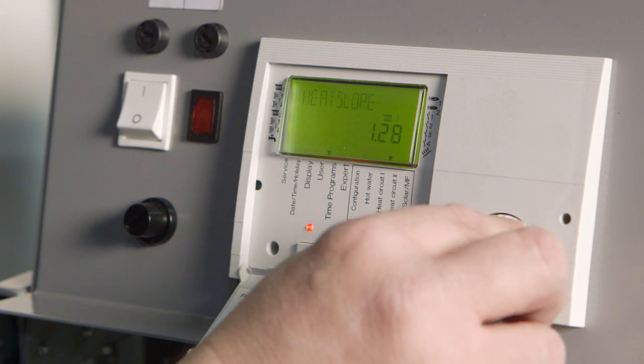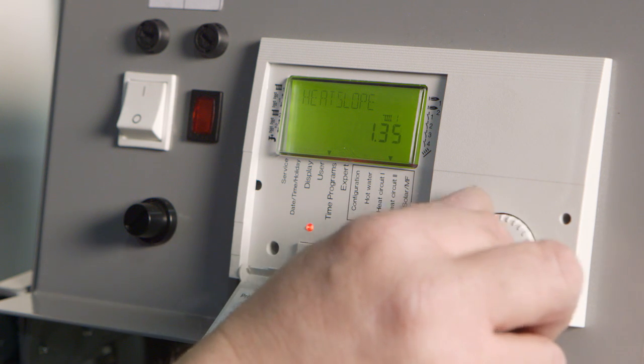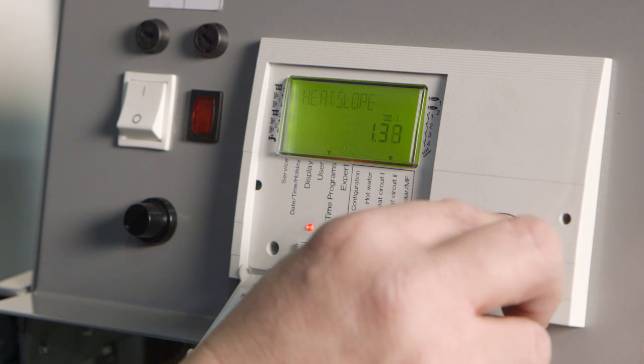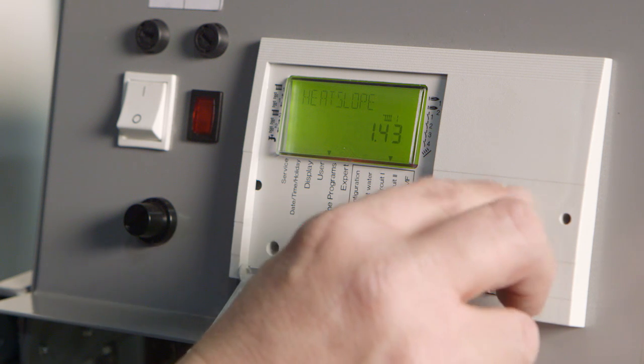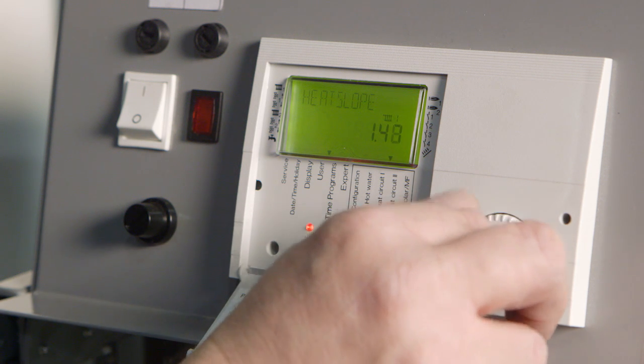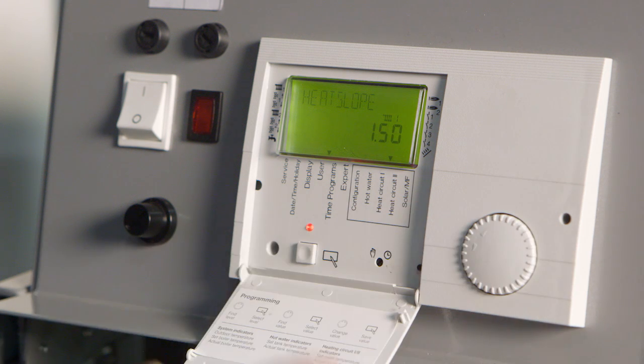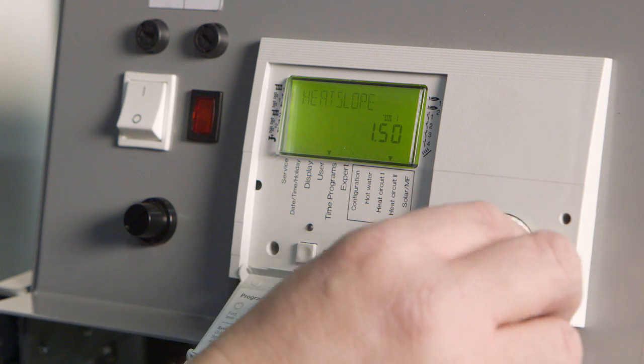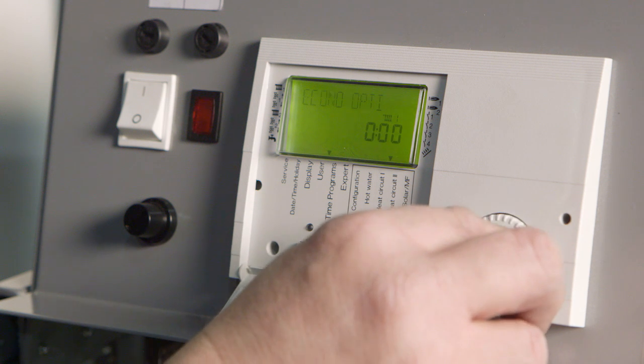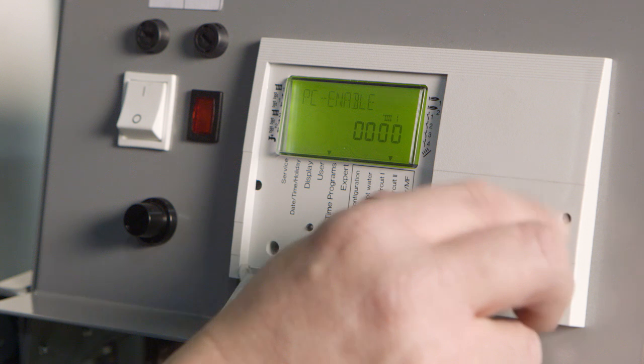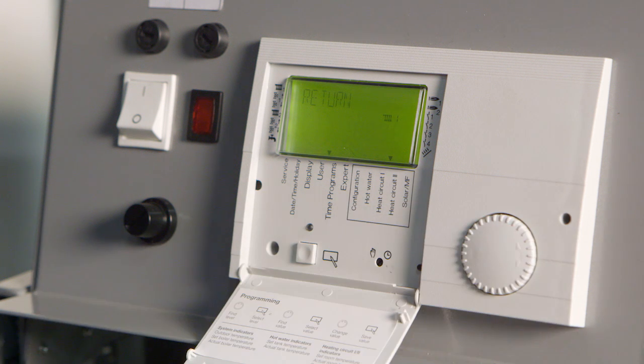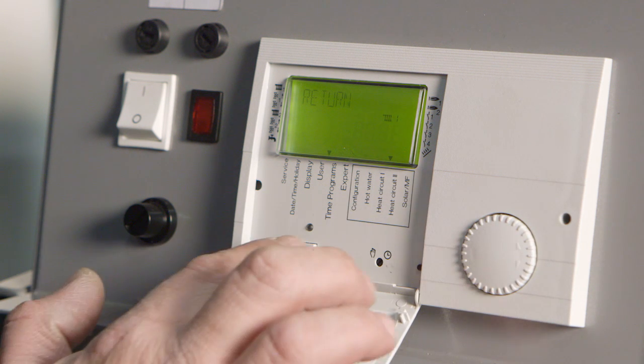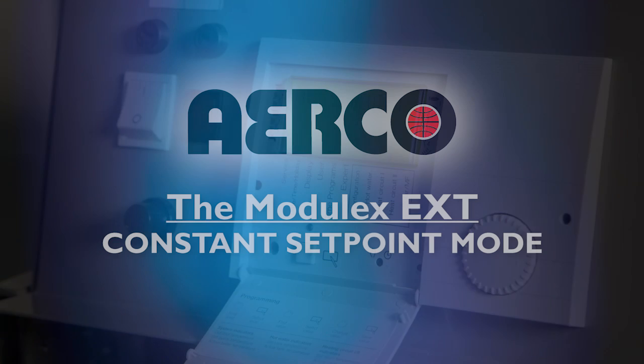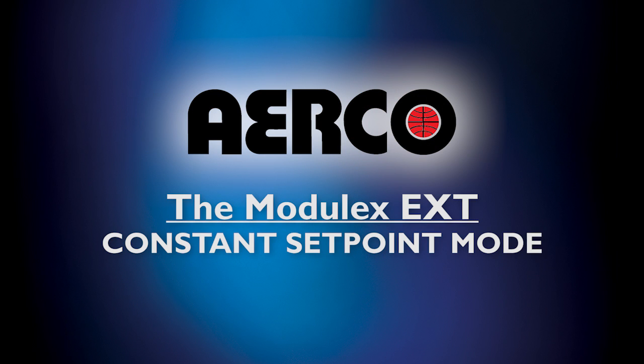Remember that the value entered must be between 0 and 3.00. You can find the desired value by turning the rotary knob as shown. Press the program key again to store this value in your system's memory. Scroll back through the HTG Circuit 1 submenu until Return appears. Then, press the program key again to exit this submenu. Constant set point mode can be used when you want to set a fixed header temperature.